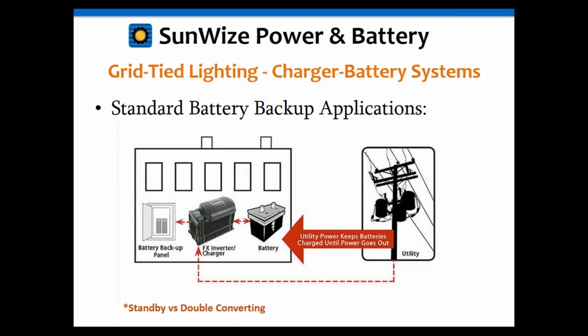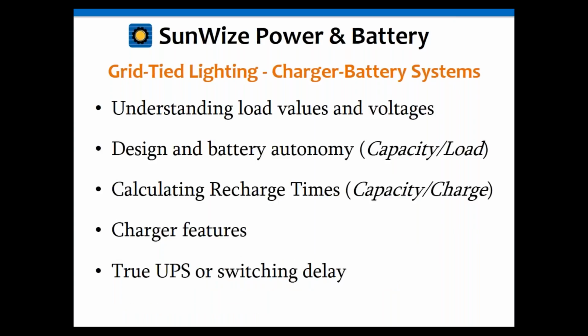Okay, I'm just going to briefly cover some of the grid tie stuff now. And again, this is where the utility is going into an inverter charger, and then going to battery. Similar to a PV system, for the standalone, you need to understand your loads, its values and voltages. And this is especially important when it comes to battery autonomy. So you're going to actually handle this in some regards the same as you would a standalone PV system for the initial part of it in terms of the battery sizing and for understanding the loads.